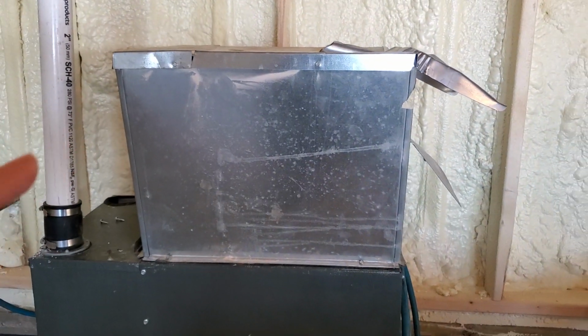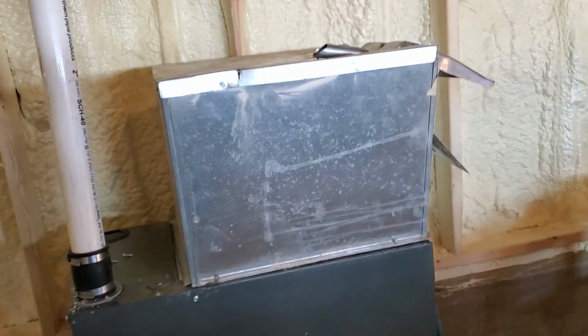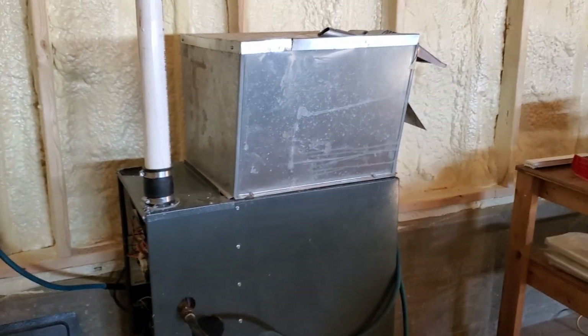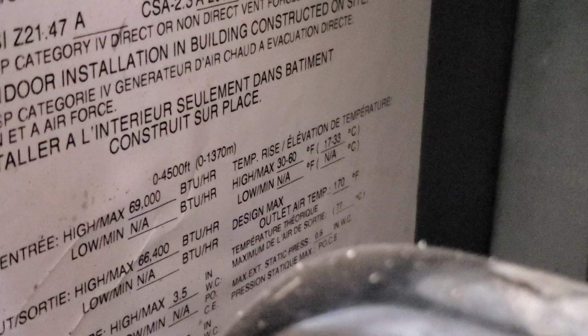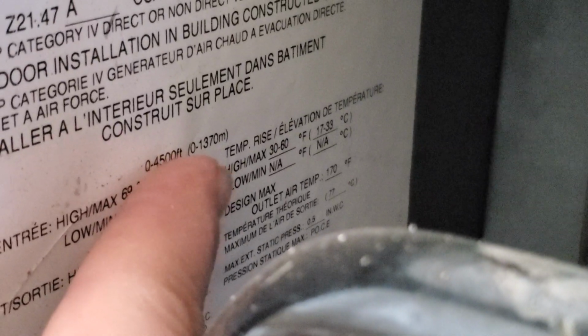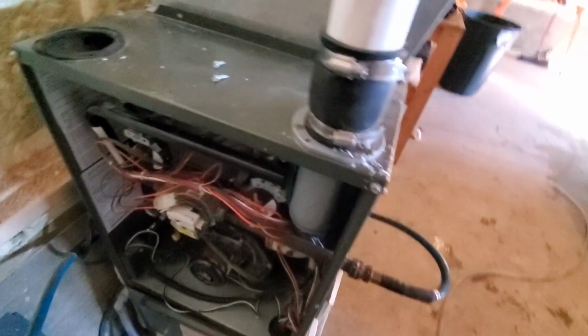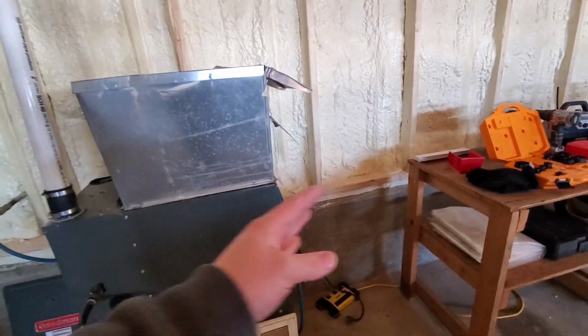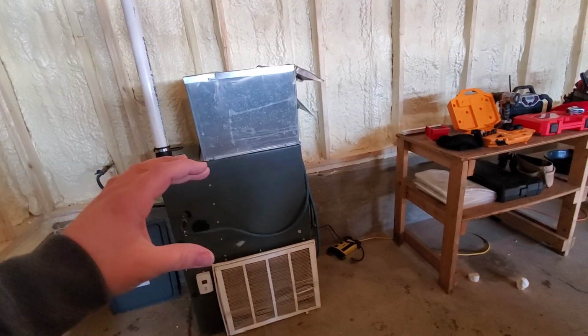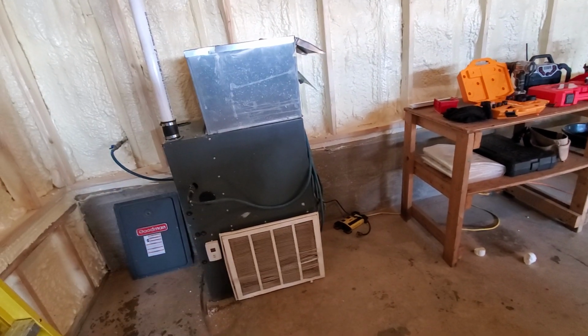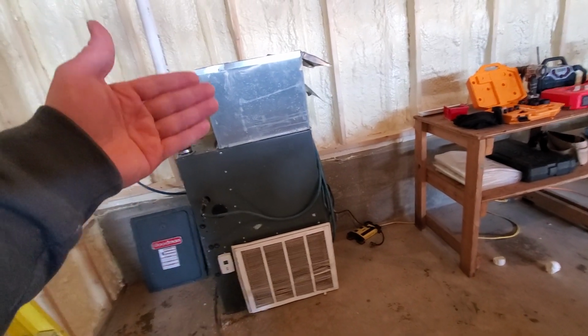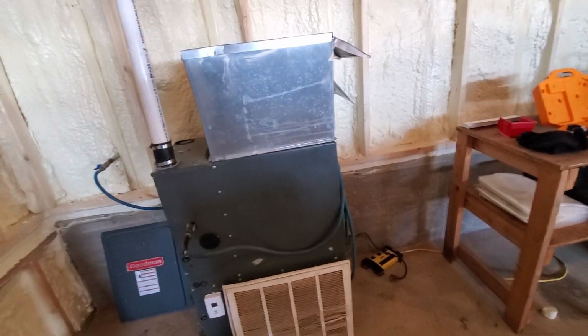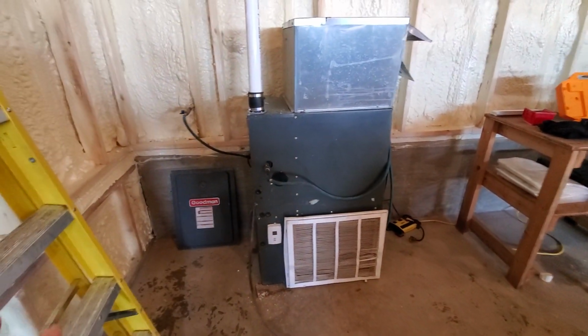Anyway, so put some kind of a plenum to reduce the amount of air going through the furnace so that you don't overcool that heat exchanger. And you can always check your temperature rise. See right here it says the temperature rise should be 30 to 60 degrees Fahrenheit. So the way you would test that is you just test the temperature of the air coming in and the temperature of the air coming out and make sure it's in that 30 to 60 degree range. If it's too low, if you have like a 20 degree temperature rise, then you know you're moving too much air. If it's like a 70 degree temperature rise, then you know you're not moving enough air. So that's kind of an easy way to check to make sure that you've set it up properly.